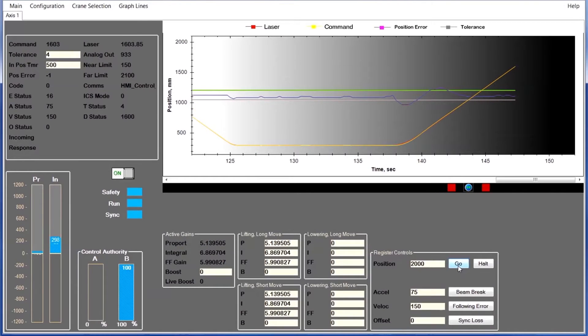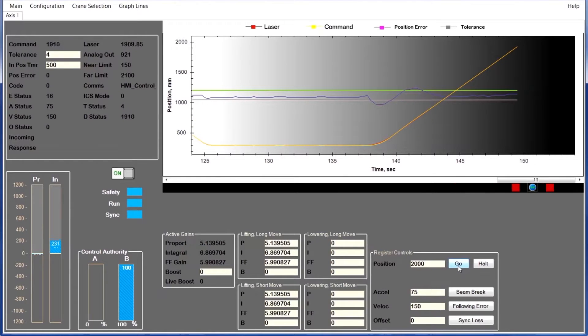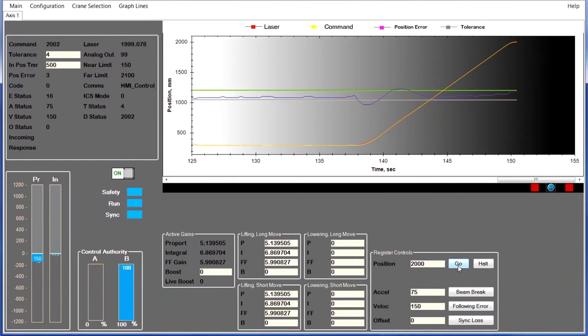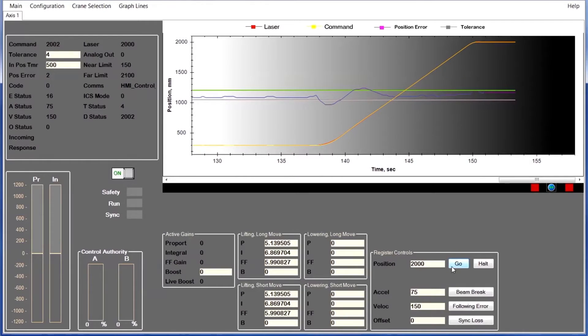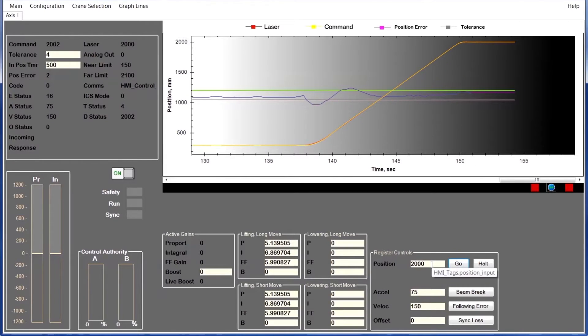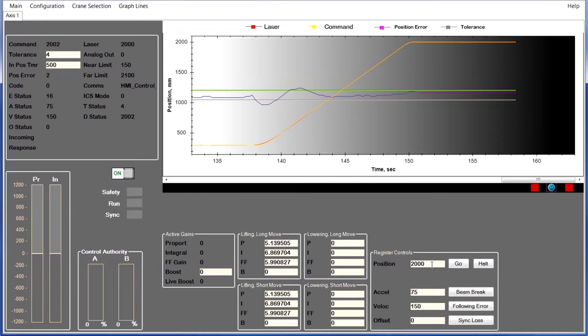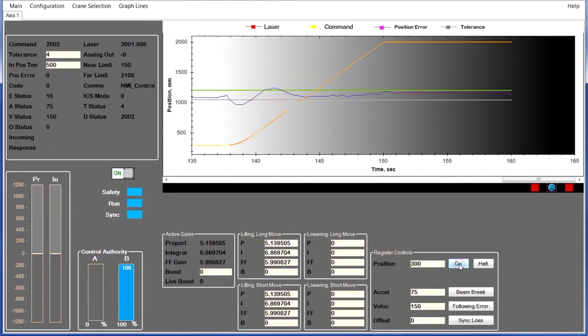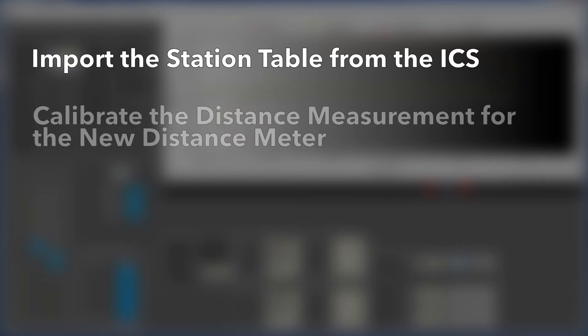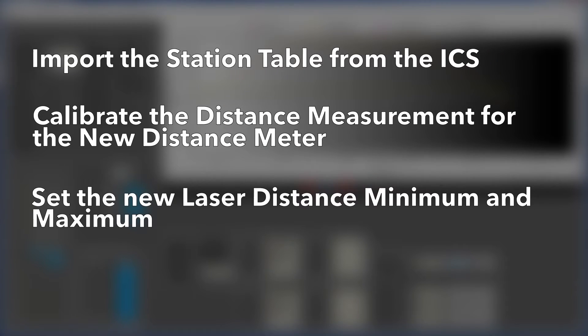The new PLC-based solution can be quickly configured to control the equipment with TrueMotion Analyzer, the Windows-based interface for adjusting the configuration and tuning of the Cybex or ABICS system. Using TrueMotion Analyzer, the startup engineer can import the station table from the ICS, calibrate the distance measurement for the new distance meter, set the laser distance minimum and maximum, and tune the motion loop.